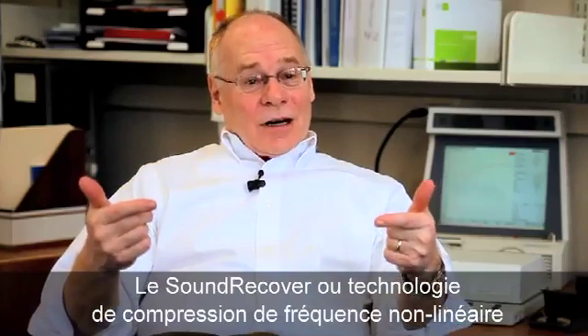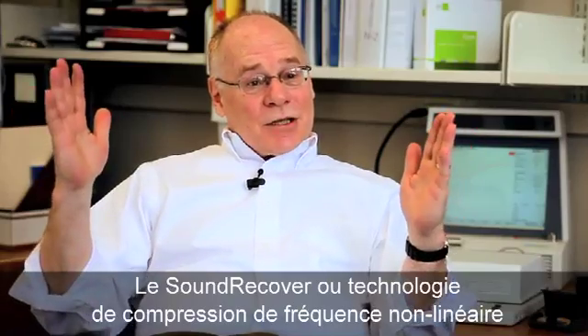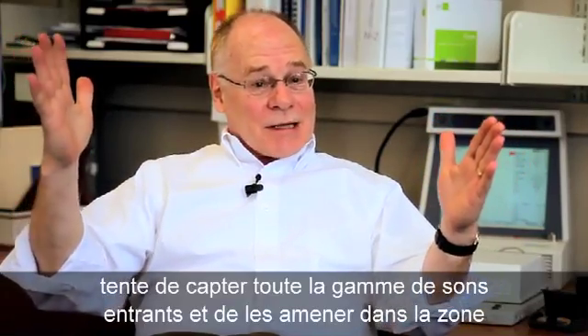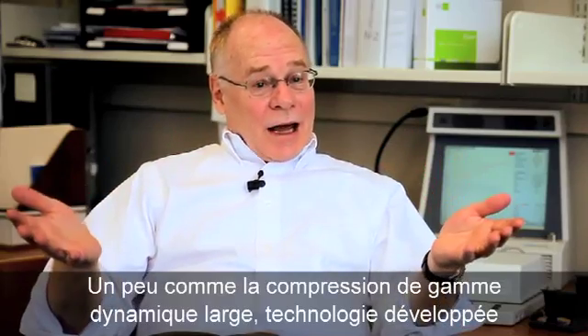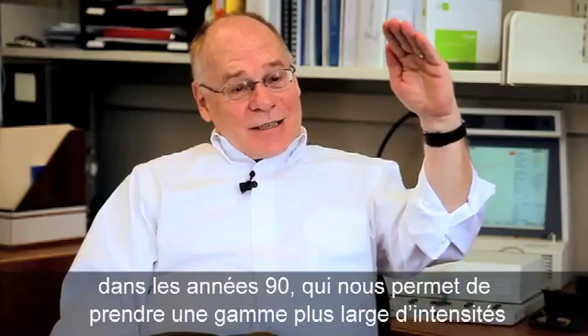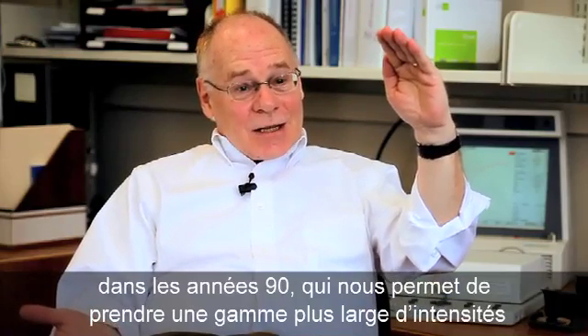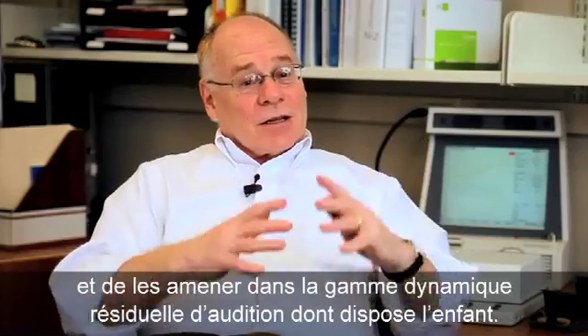Well, this is a technology that I think we've been waiting for a long time. The SoundRecover, or nonlinear frequency compression technology, attempts to take the full range of incoming sound and to bring that into the auditory area of the child with hearing loss. Much like wide dynamic range compression, which is a technology that was developed during the 90s, allows us to take a wider range of intensities and to bring that into the residual dynamic range of hearing that the child has.